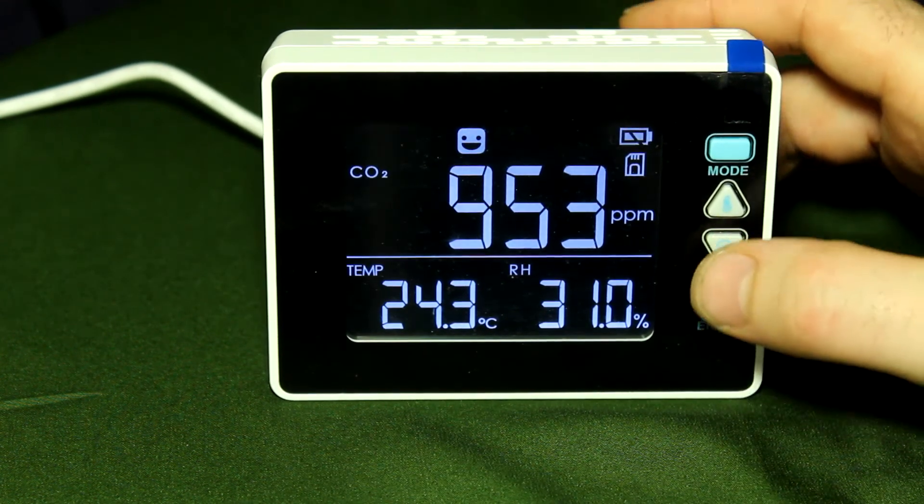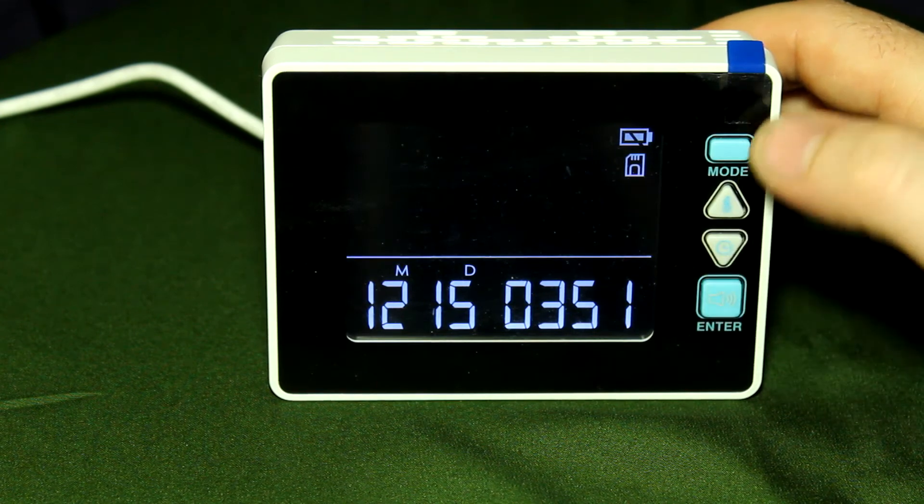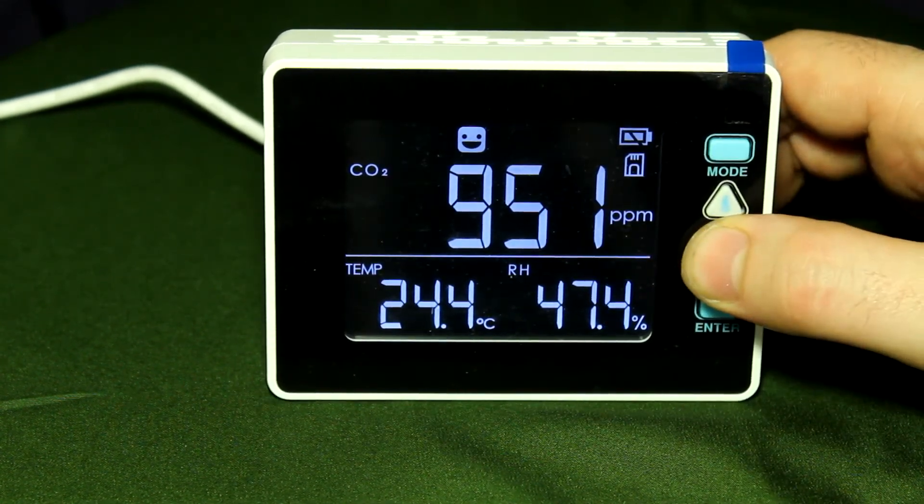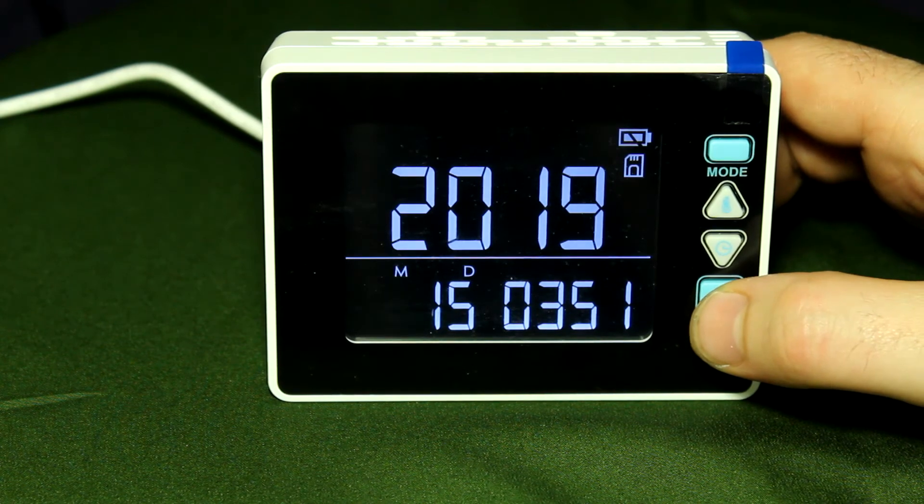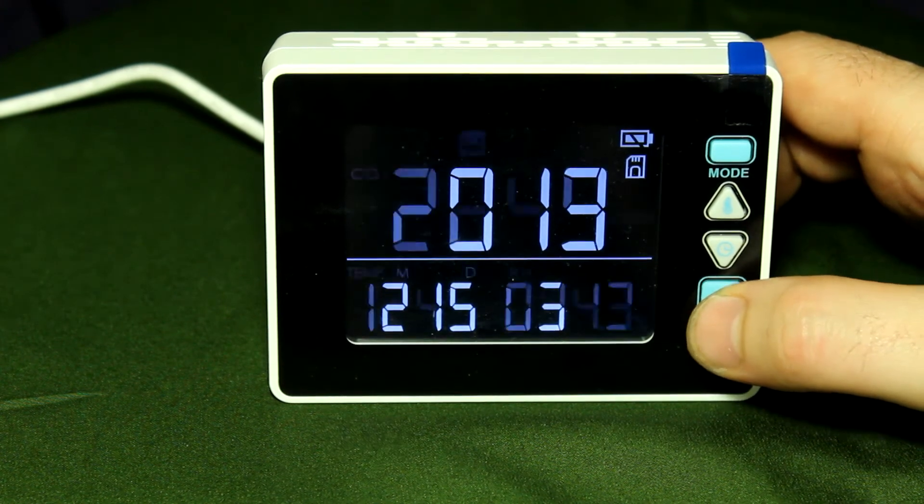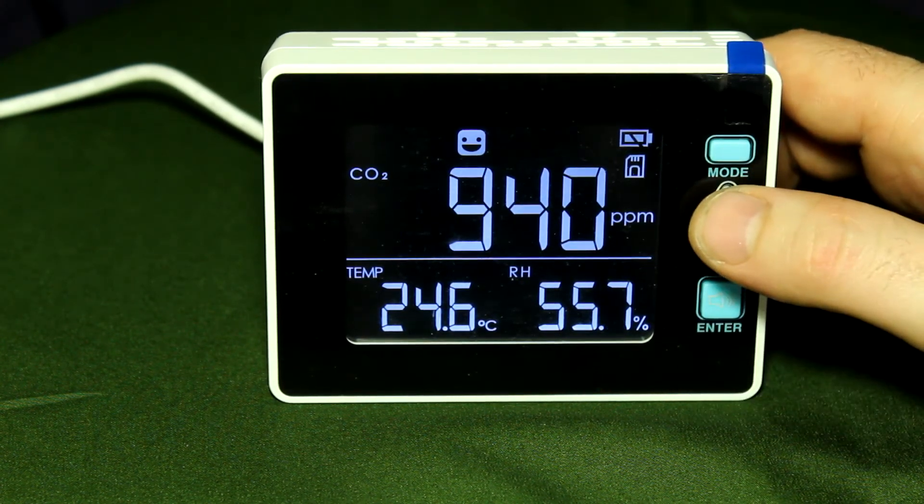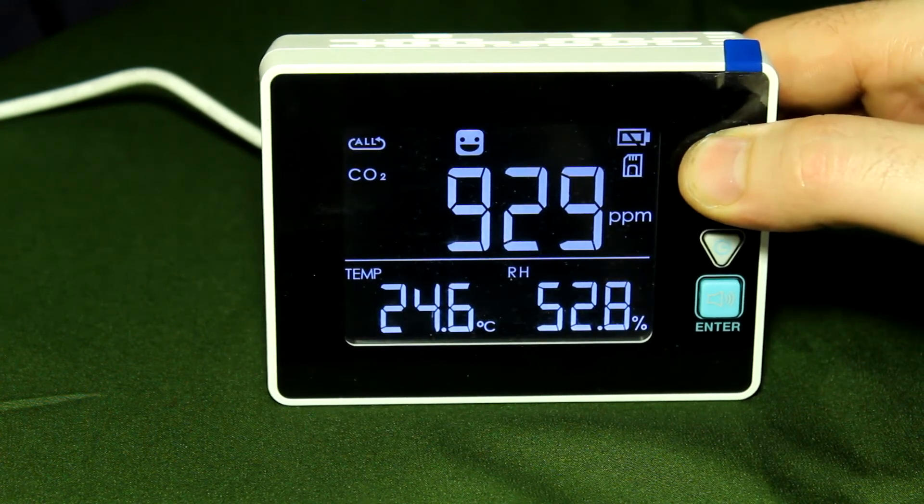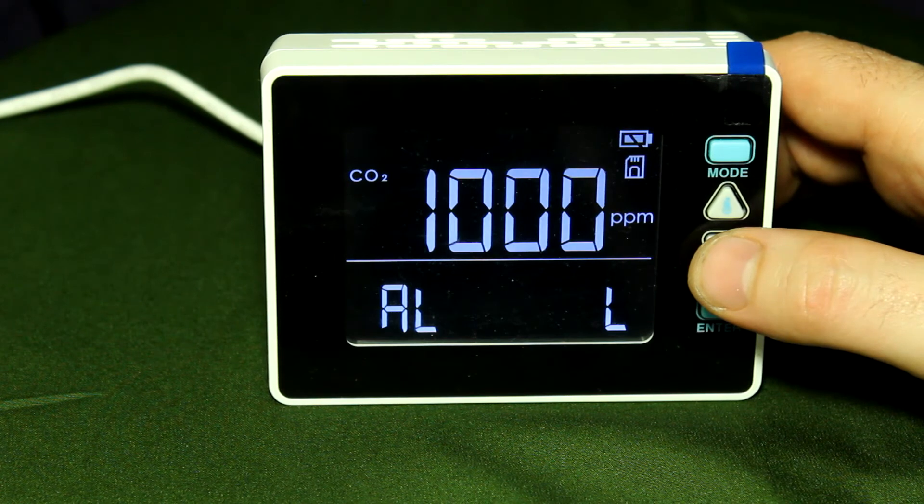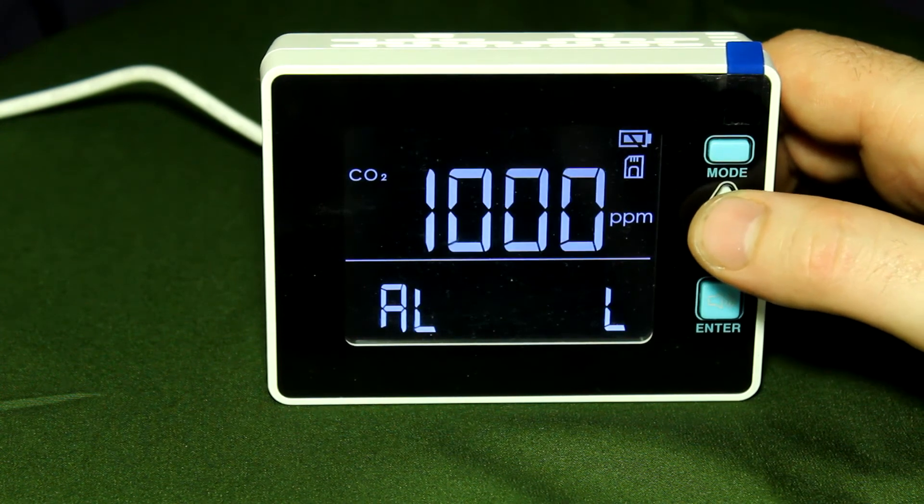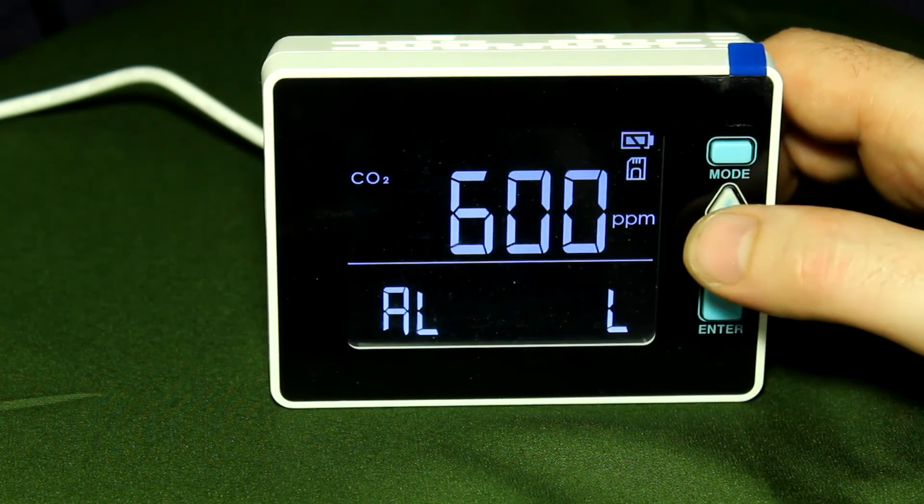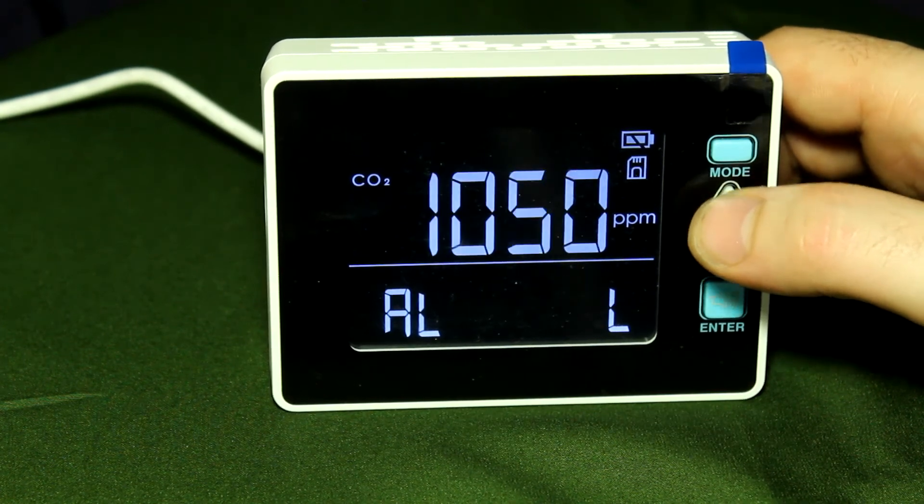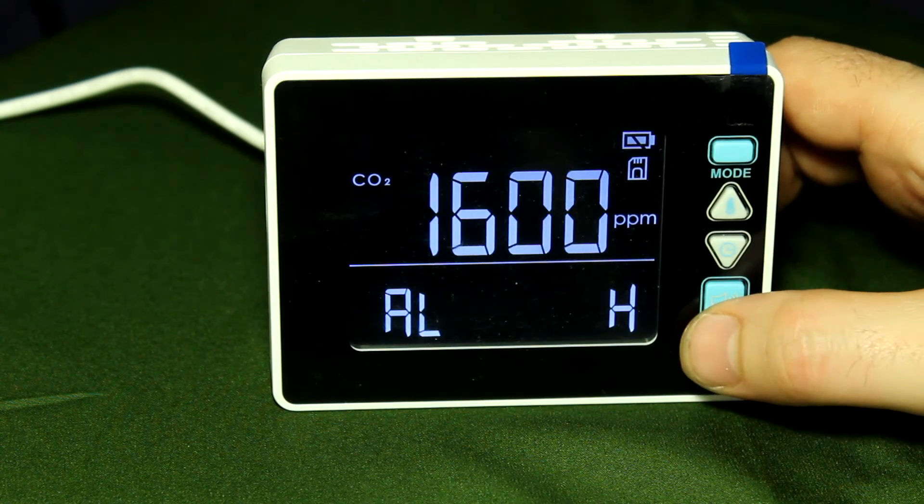I'm going to show you how to do some basic stuff. We're going to hold the down button and this is going to allow us to set up our date and time. You push the enter button to go over to the next thing you're looking to program, and then the time of day and so forth. Now we're going to hit the mode button, we're going to hold it and it's going to bring us to a new menu. This here's going to be the alarm parts per million. This is the alarm low, so 1,000 parts per million, that's going to be a low alarm. We're going to put it higher than that because I don't want it to beep all the time even though we can turn it off. Let's put it to 1,100. 1,100 seems to be a good number here.